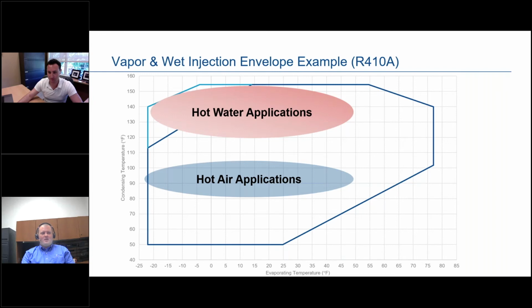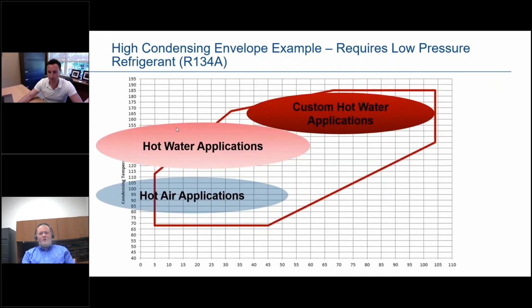Okay. Yeah, then kind of the final envelope that I'm going to show. This is a low pressure refrigerant, so R134A. In the future, it might be an R513A type of system because that's got the low global warming potential as well. But as you can see, there's limitations on what that evap temperature is for saturated suction. So a lot of these systems require a higher evap temperature. So it can be a ground loop system or something similar to that in order to keep that evap temperature high in order to make very hot water.